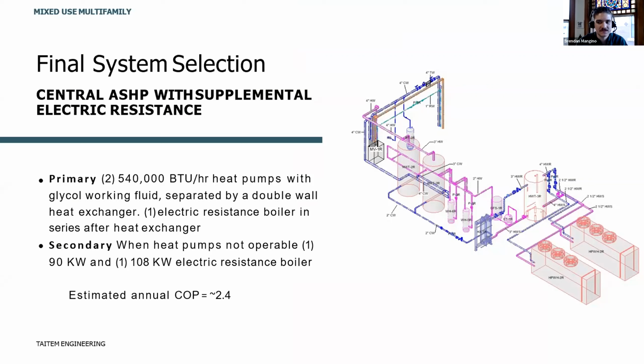But the way this system is designed, it's 2 R-410A heat pump systems. They're both 540,000 BTU per hour. And we're using glycol as a working fluid for this system, separated by a double wall heat exchanger. And then we also have an electric resistance boiler using a close spaced tee injection type arrangement as supplemental to bring that up to the target temperature of 140°F, because right now we're probably going to get 125 just with the heat pumps. The secondary system, for when these go down because of ambient temperatures, would be 2 electric resistance boilers.